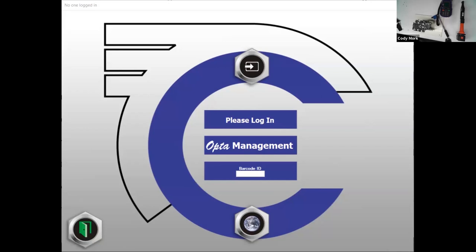And we'll give it about 15 or 20 more seconds if nobody has questions. But looks like here's one. How does the click dip work? So the click dip works. What it's looking for is that first click. So as we are ramping up on our torque scale, that click wrench is going to click, and it's going to see a peak in torque, and then it will drop down X percentage. When the software sees that drop in torque, it then records that first peak instead of that second peak, because usually an operator is going to pull past that first click and there'll be a higher peak torque after that.